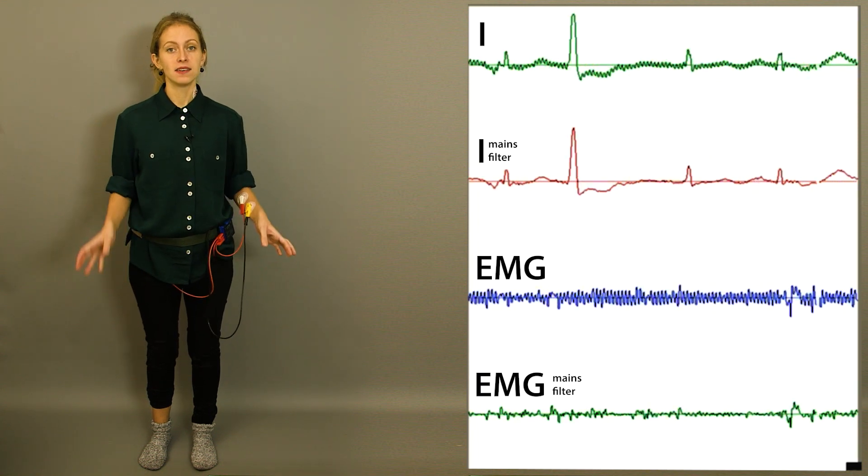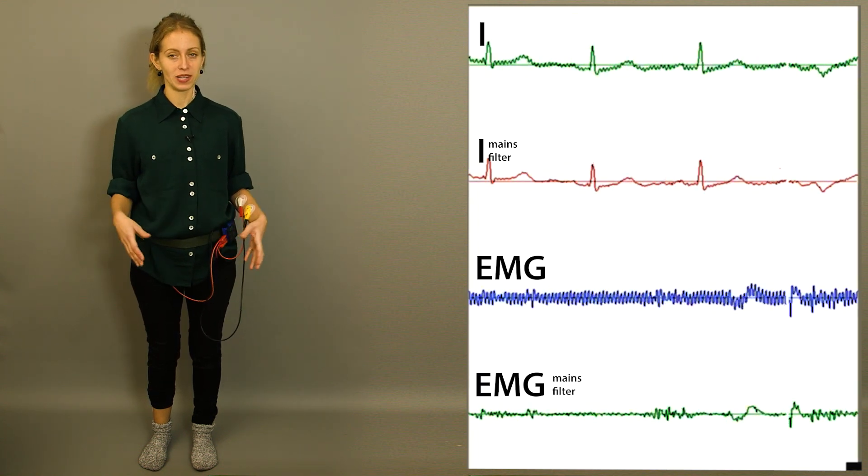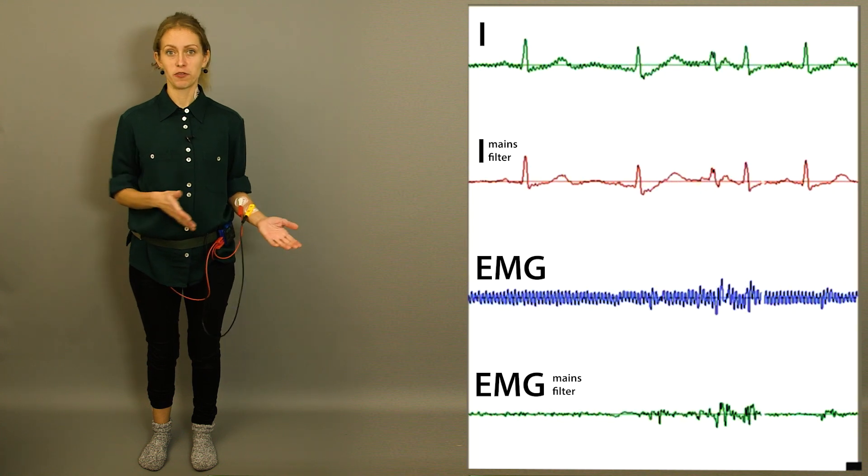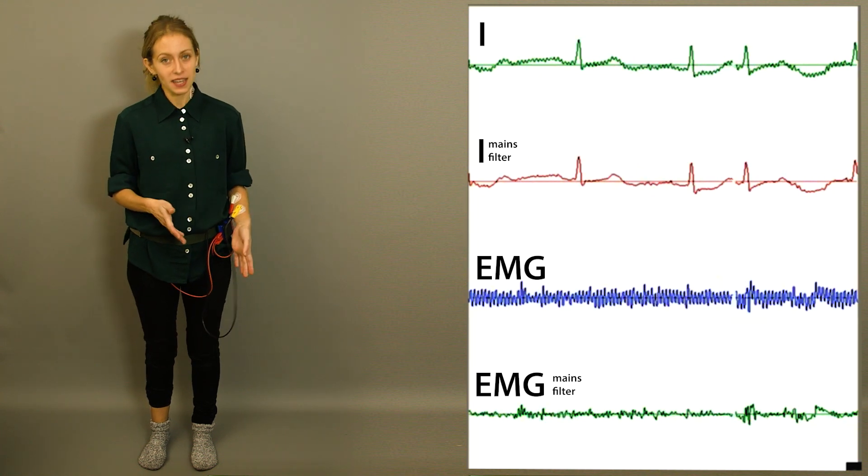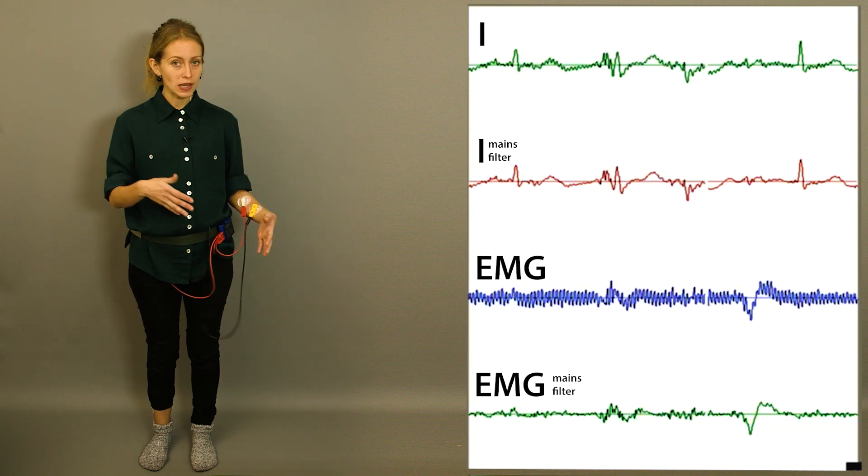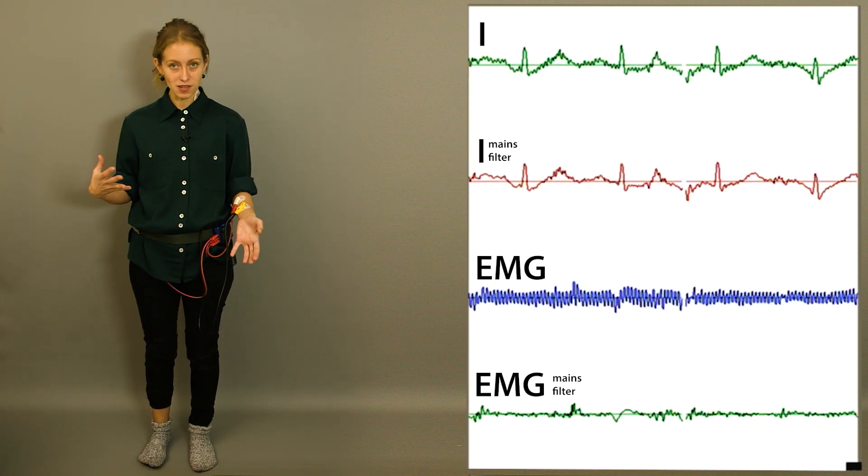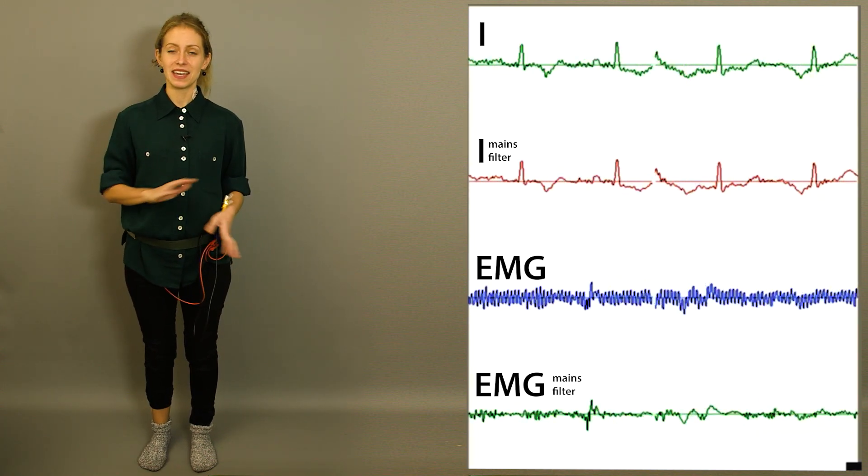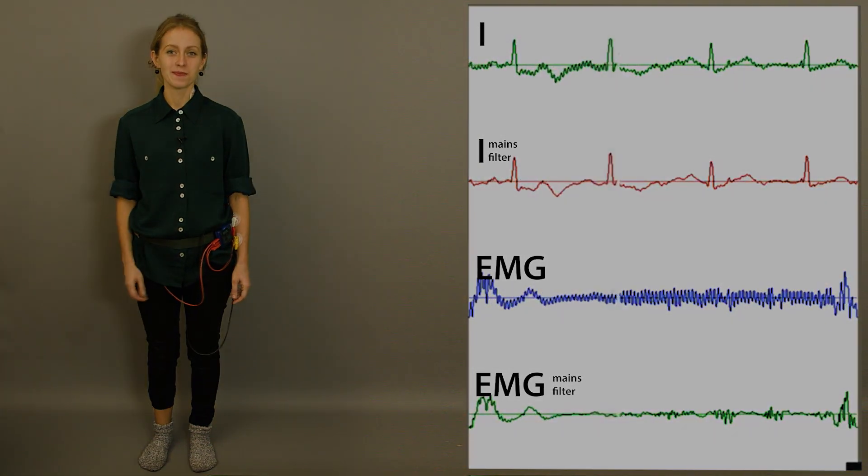In the old analog days, three electrodes were absolutely necessary to get rid of power line interference, whereas today we can equally use two electrodes plus a power line filter and eliminate any power line interference.